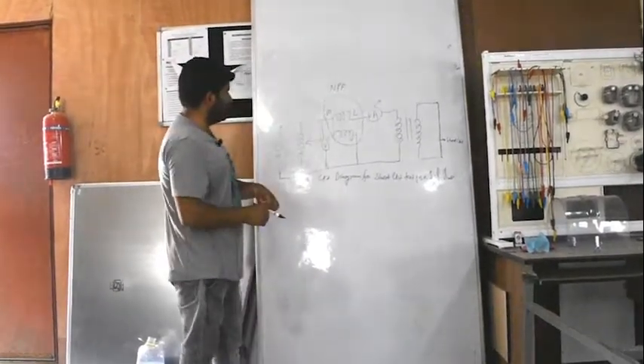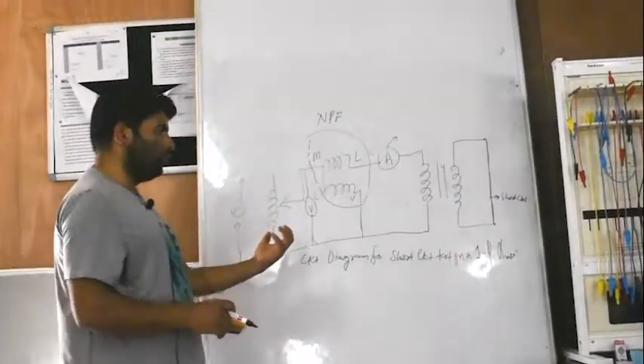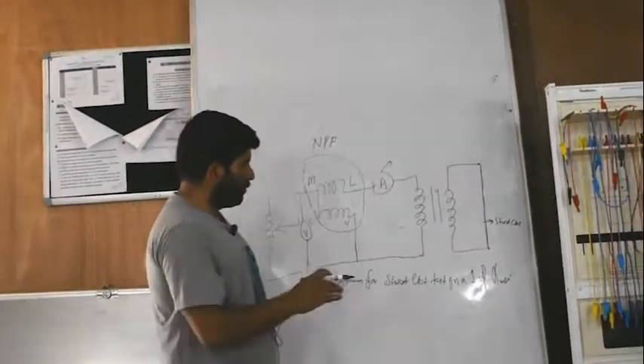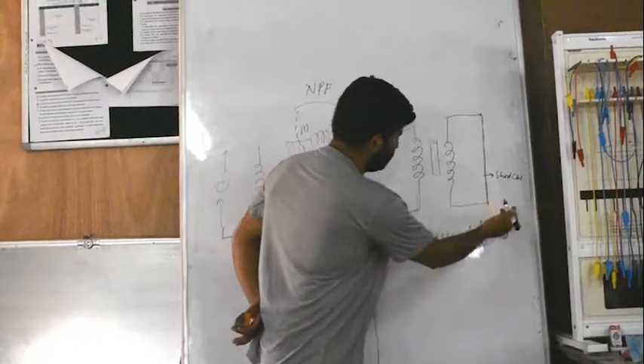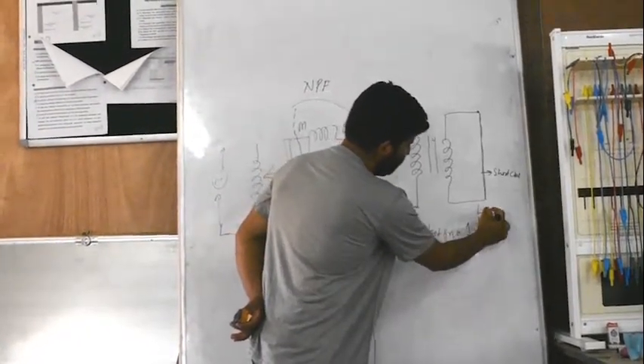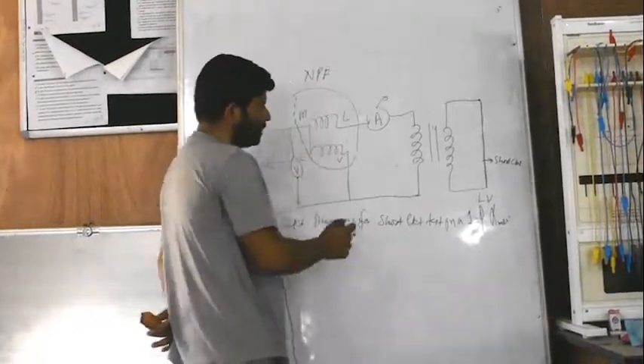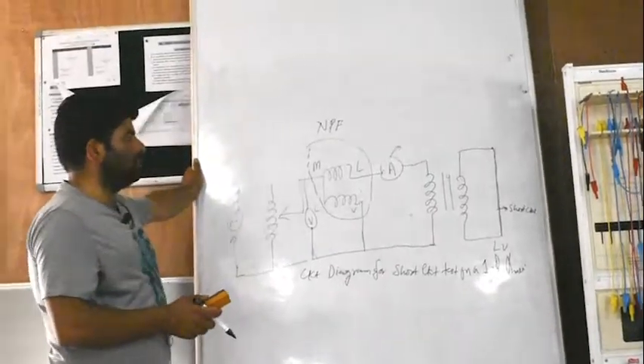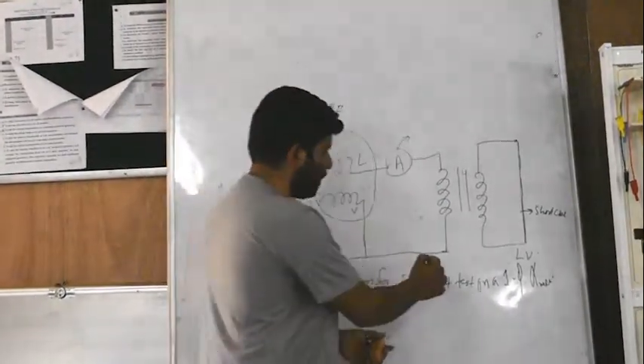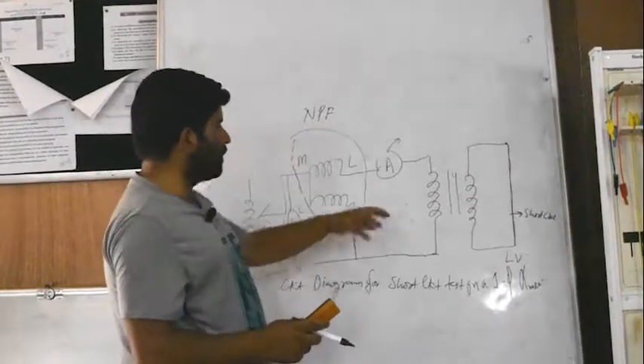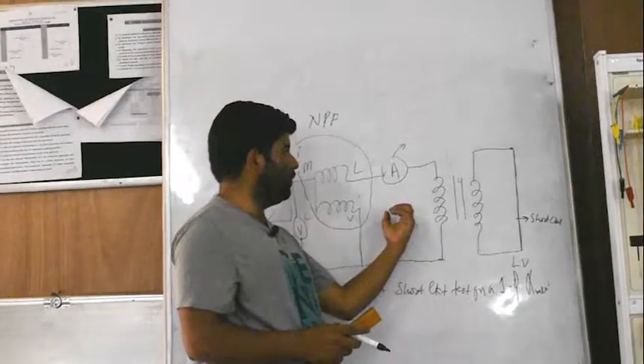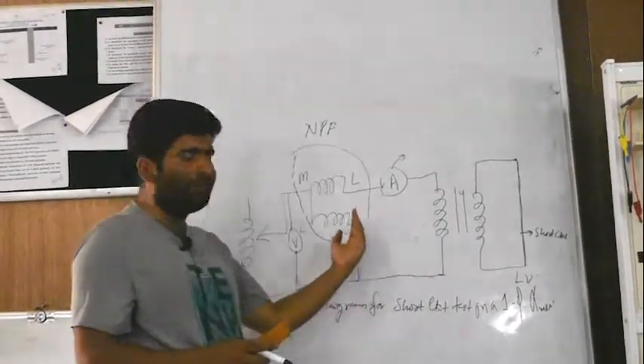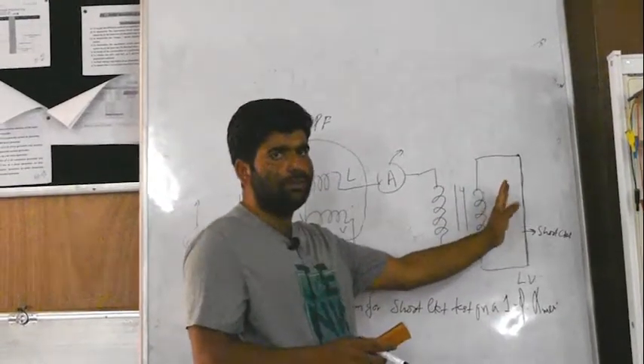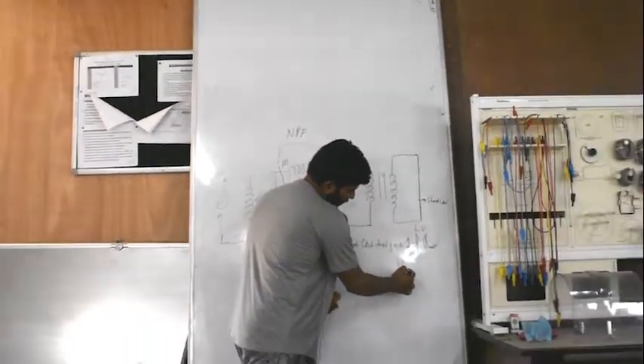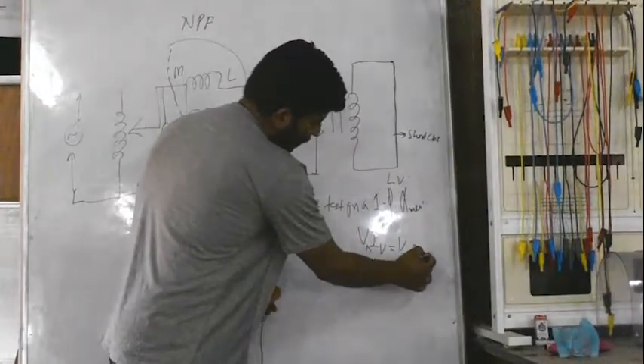Now previously I have told you that in the no load test, we are performing it on the low voltage side, keeping the high voltage side open circuit. In this test, we usually short circuit the low voltage side and perform the experiment on the high voltage side, because, as you know, in a transformer the primary VA and the secondary VA are equal. So the short circuit current on the high voltage side, or the rated current on the high voltage side, will be comparatively lower than the rated current flowing on the low voltage side, because this product V high voltage side times I high voltage side will be equal to V low voltage side times I low voltage side.